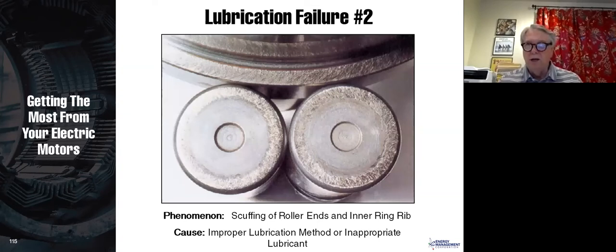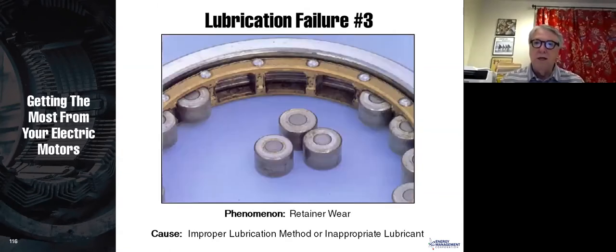Here's one. Take a look, and you can see that these are the roller ends, and you can see how they're scuffed around there. So that scuffing also is an indication of either improper lubrication method or an inappropriate lubricant. And we talk quite a bit about the proper way to lubricate. Many people are not lubricating properly, and if they did that, they would see much better reliability out of their motor. So this is one of the things that can happen.